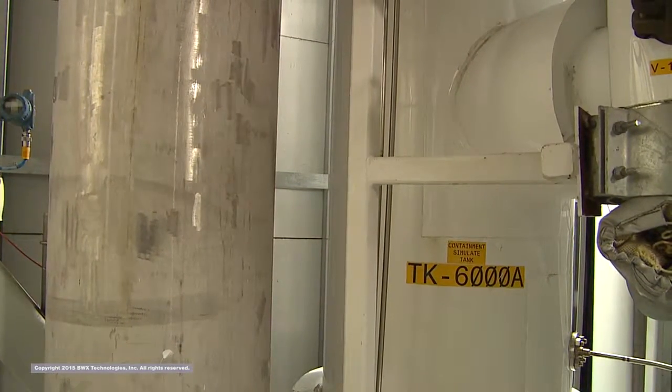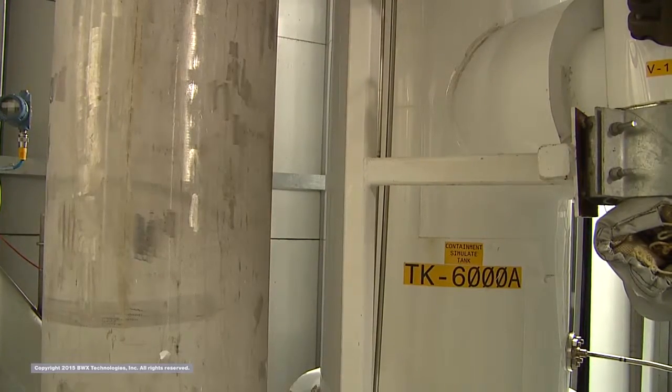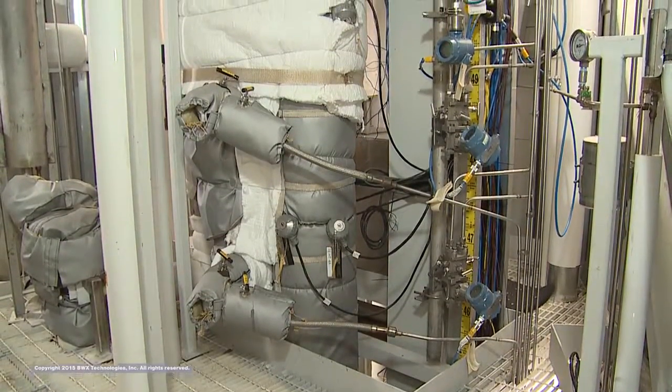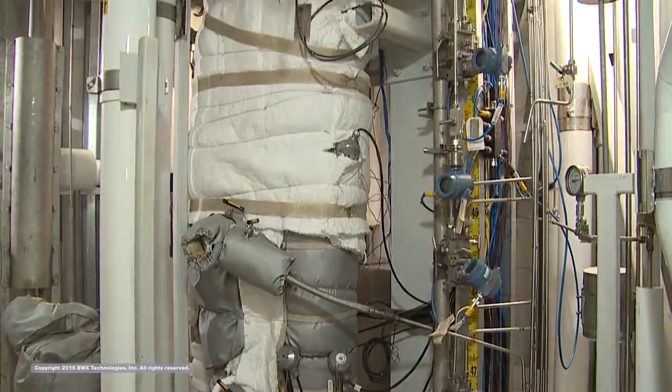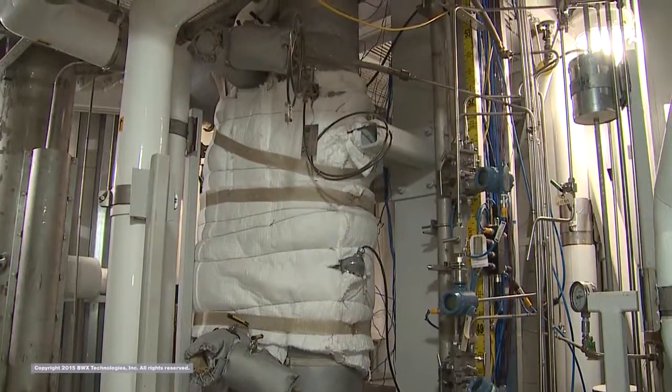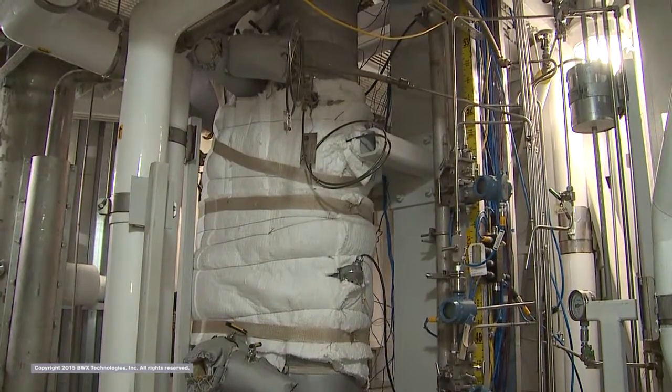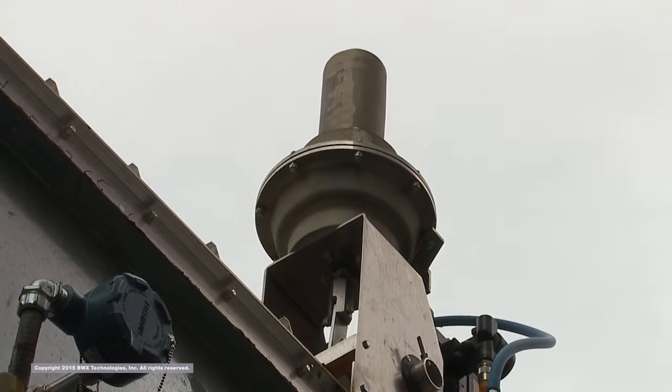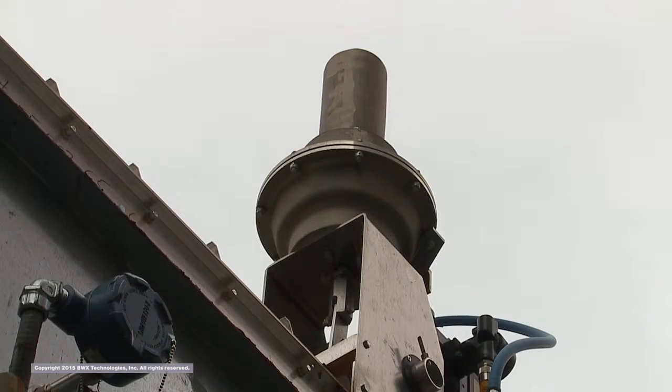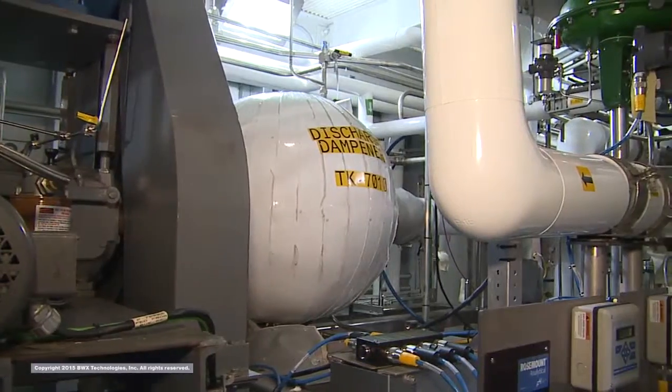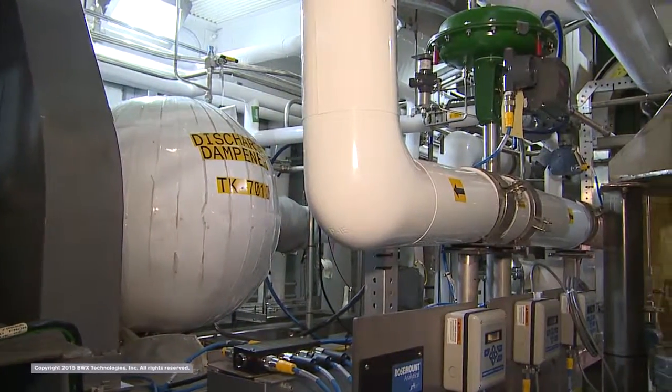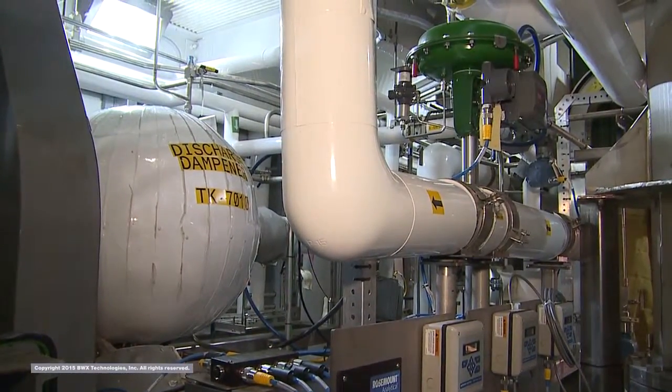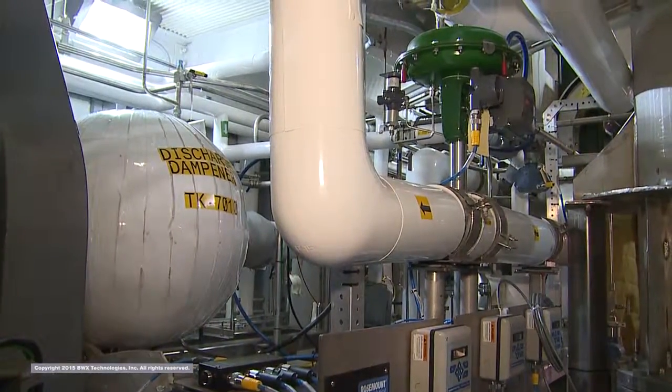The balance of plant includes the feedwater, steam, and condensate systems which are simplified for the IST since power generation is not included. The IST's housing provides several convenient locations for tapping into the steam line for additional testing opportunities. The feedwater flow control valve can be modulated to match the power demand, including simulating load-following scenarios.